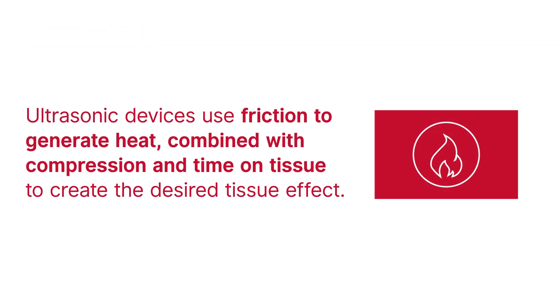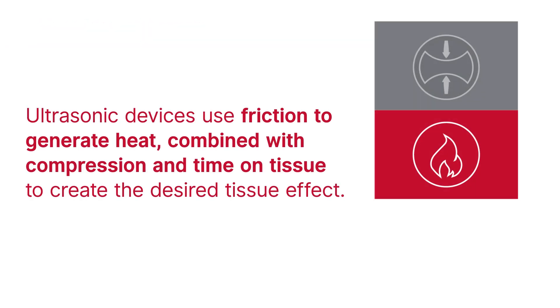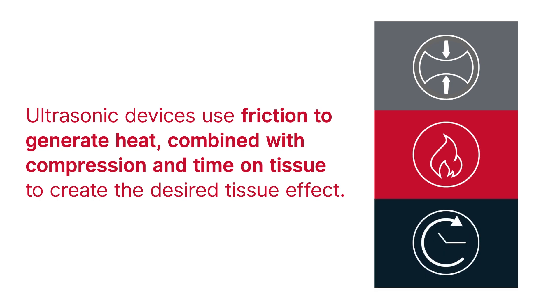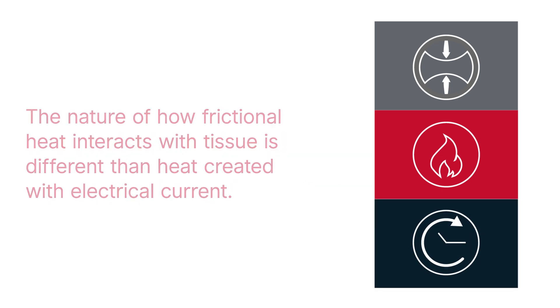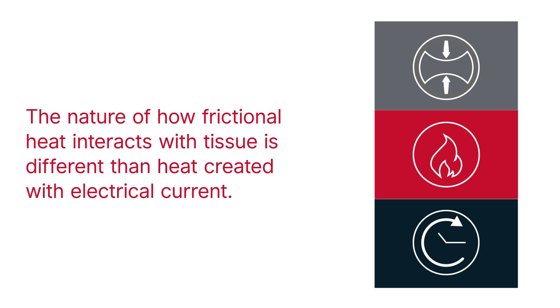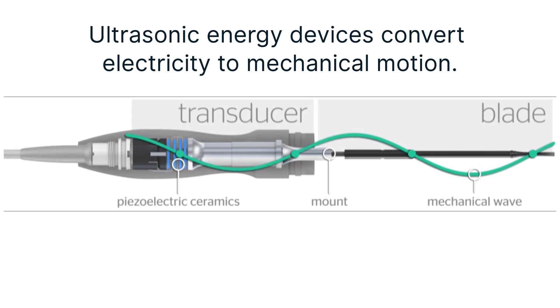Ultrasonic devices use friction to generate heat, combined with compression and time on tissue to allow surgeons to create the desired tissue effect. The nature of how frictional heat interacts with tissue is different than heat created with an electrical current, as you will learn in the monopolar and bipolar videos in this video series. The way in which ultrasonic energy devices convert electrical energy to mechanical motion is critical to understanding the concepts in this video.